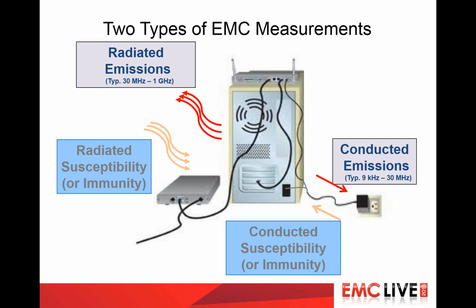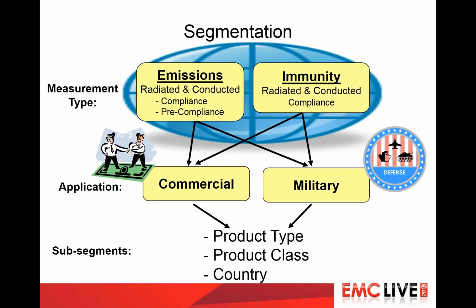There are some cases where medical equipment is tested for immunity here in the U.S., but that's not required by the FCC. That's required by the medical board to put some items in the hospital. We'll have a slide that talks about the immunity testing so you can see what it requires, but it is not required by the FCC.